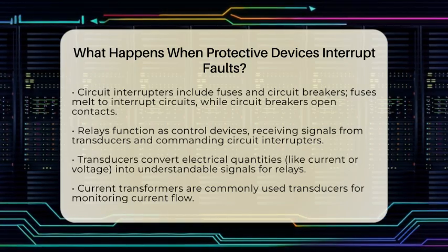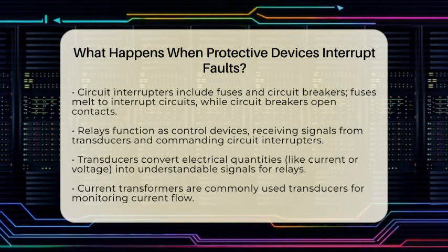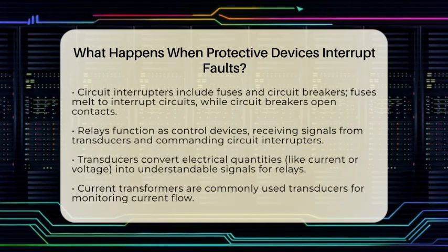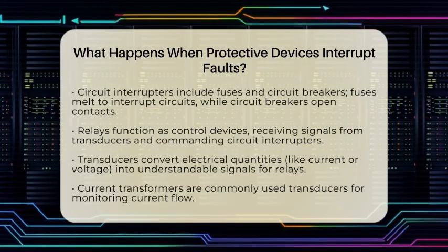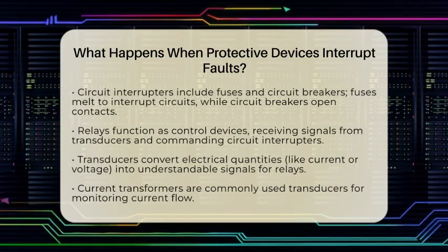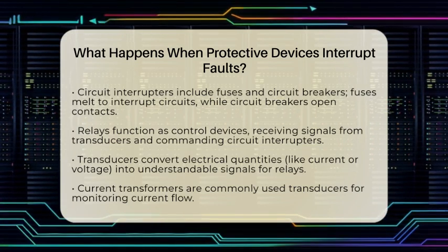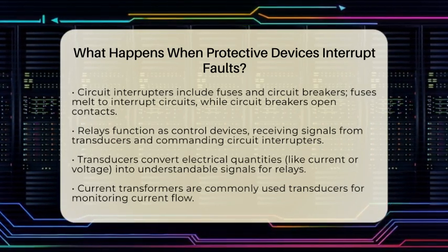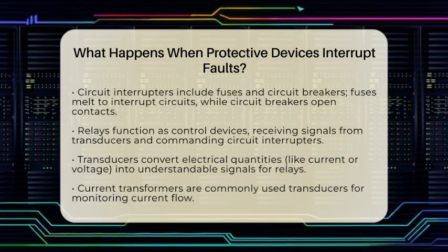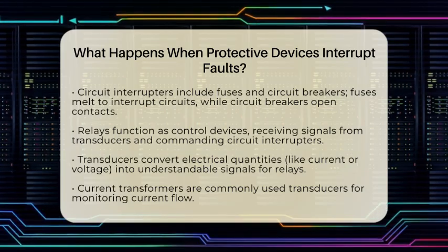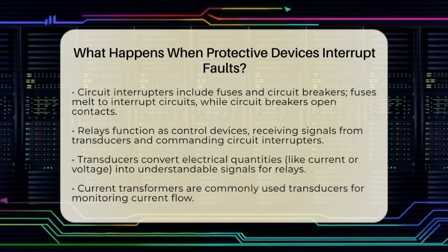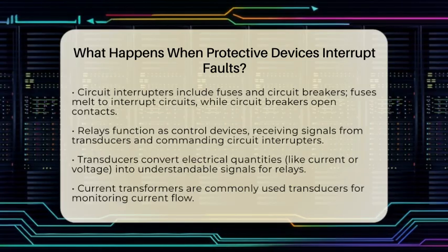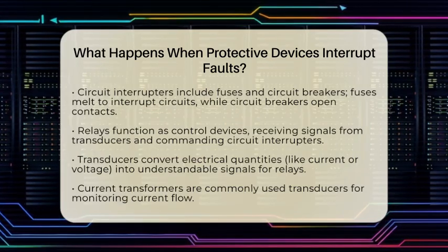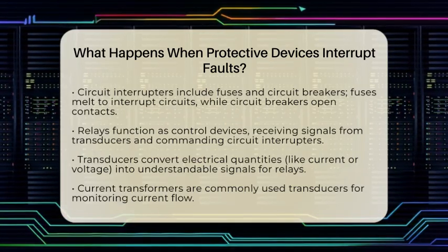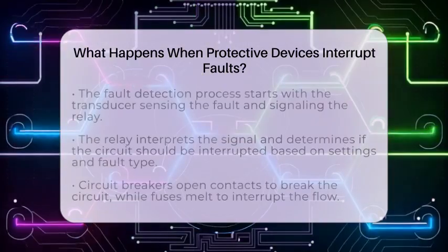Transducers convert electrical quantities, like current or voltage, into signals that relays can understand. For fault detection, transducers often include current transformers that monitor the flow of current in the system. When a fault occurs, the process begins with detection. The transducer senses the fault and sends a signal to the relay, indicating that the current has exceeded safe limits or that there is an imbalance in the system.